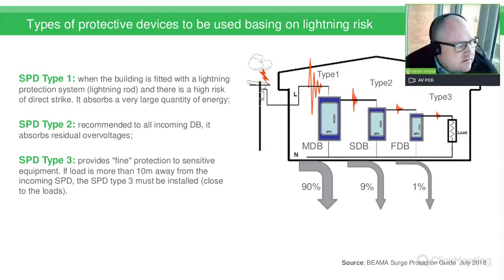Surge protection devices are split into three different categories: type 1, type 2, and type 3. I'll just take a few minutes to talk through these. The SPD type 1 is fitted when there is a lightning protection system or a lightning rod, and there's a high risk of a direct strike. It absorbs the very high quantity of energy at the point of intake. A type 2 is recommended for all incoming DBs. It absorbs the residual overvoltages. So we have a system approach where type 1 takes the largest bolt of energy, and type 2 then filters out any that pass through the type 1. And then type 3 provides fine protection to sensitive equipment.